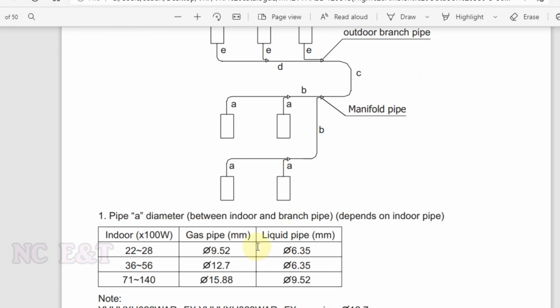This table is showing the pipe diameter for the branches for the indoor units. We can select from this table as per the capacity. If we have capacity from 22 to 28, the gas pipe will be 9.52 and the liquid pipe will be 6.35. When we go to the main after the indoor units, we will add the capacity of both the units, and from the table we will select the diameter for the branch.